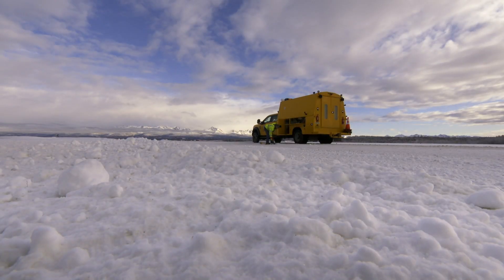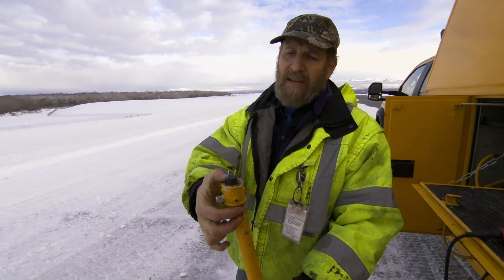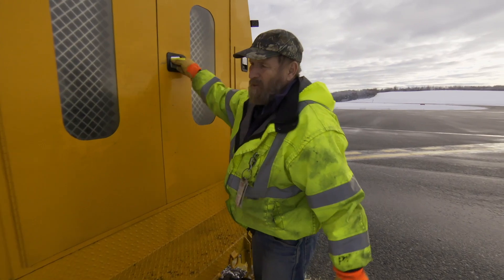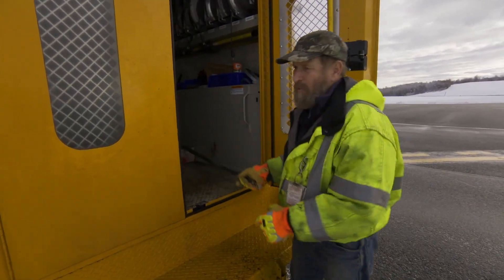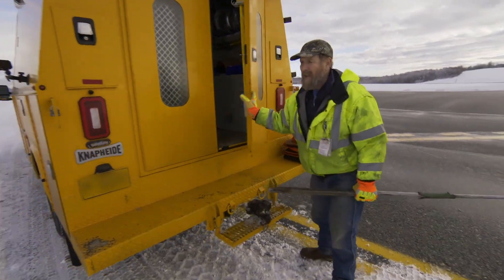The second broken light needs a little more work. Those connections are bent — we're not going to reuse this one. Two lights out in a row is really the biggest problem, because three lights out shuts down the taxiway. Whenever we see two in a row, that means it's time for some action. We really need to take care of the problem.